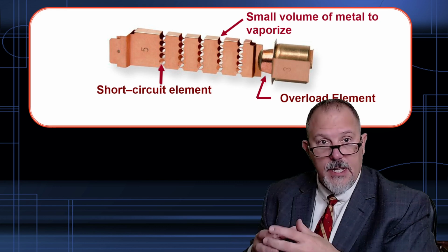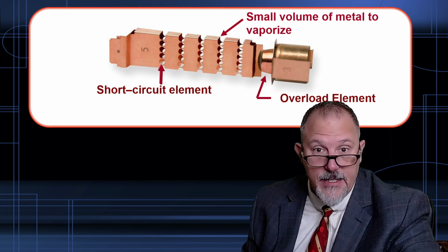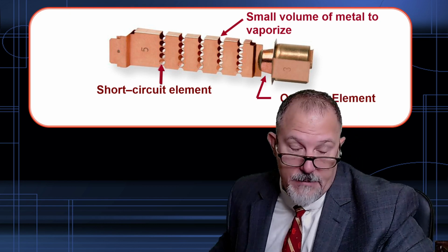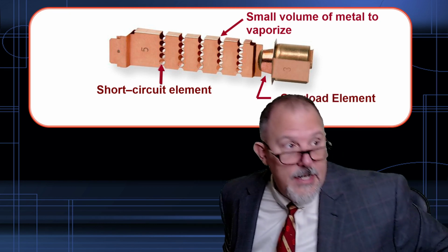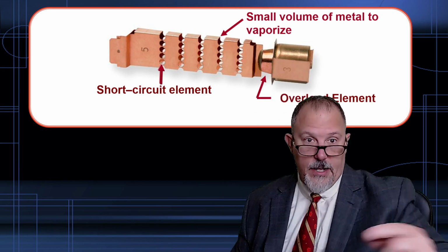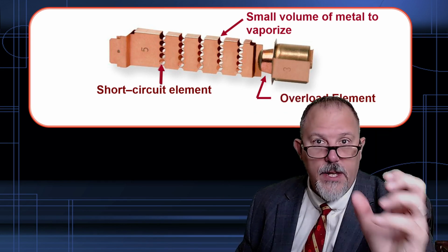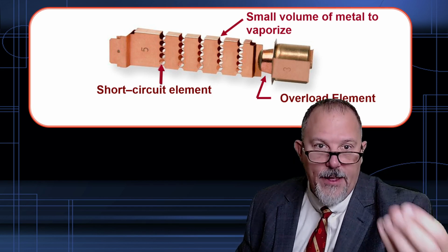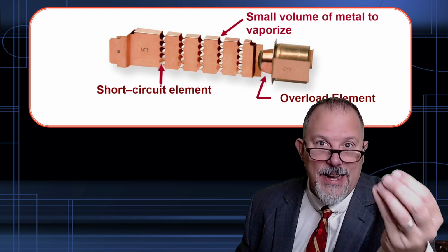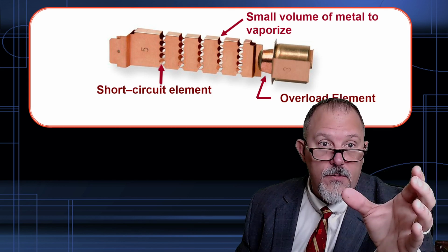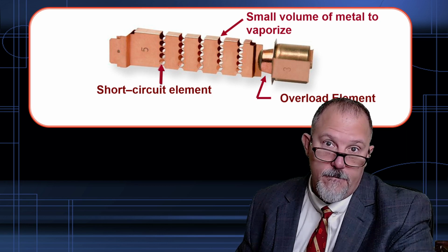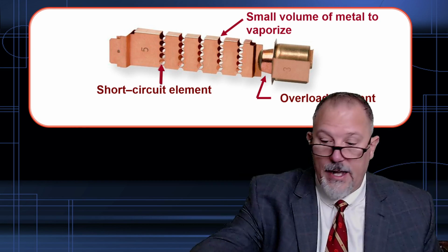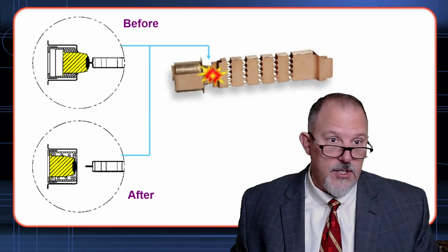And remember what happens when you heat sand. It turns into glass, or what we call fulgurite. I'm not trying to be vulgar with you, but that's what it is. What the sand does when it heats up and turns to fulgurite is add that insulation to help insulate and isolate to ensure current doesn't flow. So that's basically what the fuse element does and how it operates and functions.